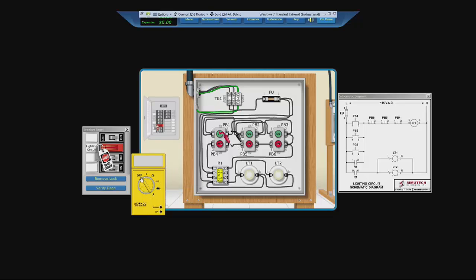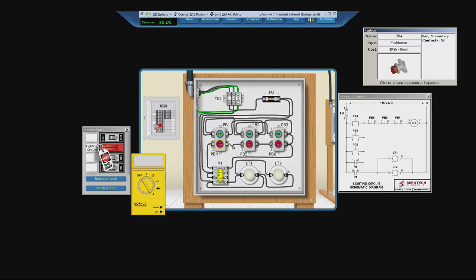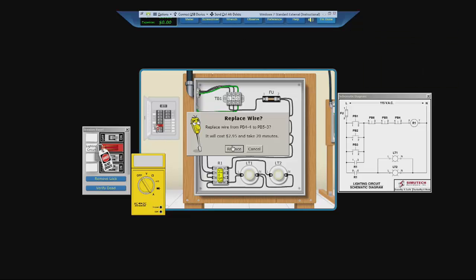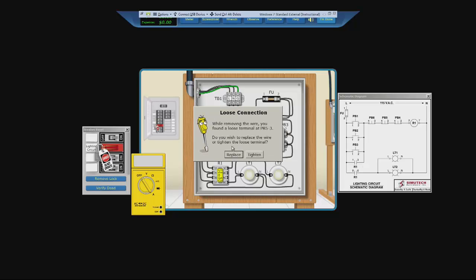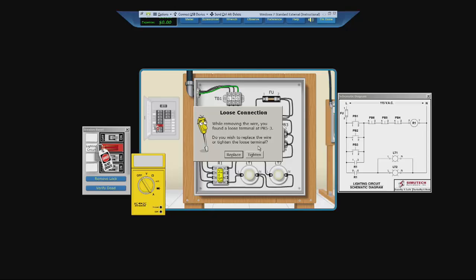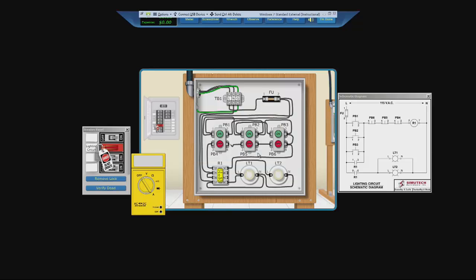So remove your leads, take out your wrench, select the wire, and replace. While removing the wire, you found a loose terminal. Do you wish to replace the wire or tighten the loose terminal? Obviously, the wire is actually loose, instead of being bad. Because of this, we'll tighten it. We don't want to spend money to replace a wire that's good.